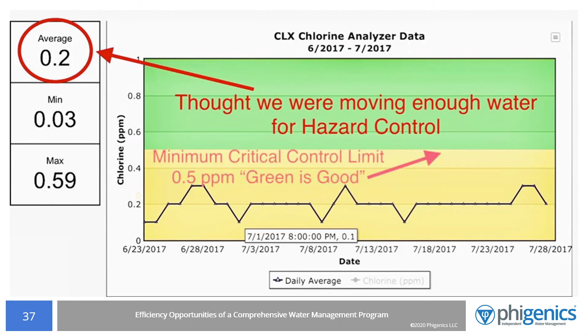They initially had housekeeping trying to flush fixtures around the facility during their daily cleaning activities. The readings, not shown on this chart, were all over the place, and there was a concern they were flushing too much water. So they installed a water age monitoring device in conjunction with the chlorine analyzer that opened a valve to flush water, but only when the chlorine fell below the set point as measured by the chlorine analyzer. So they were able to raise their average daily free chlorine level to just above 0.5 parts per million.